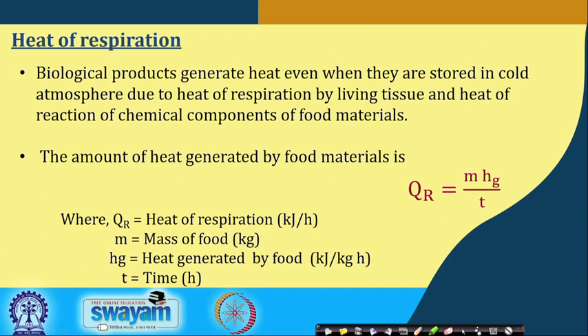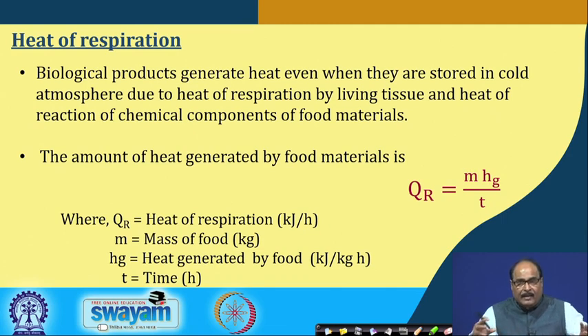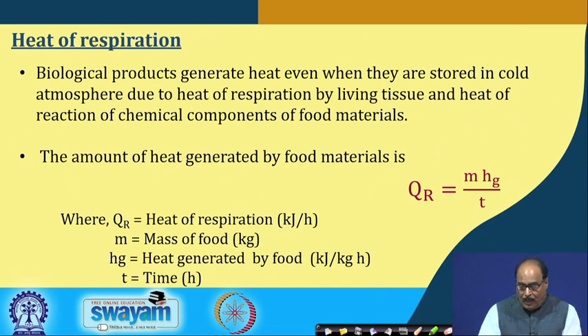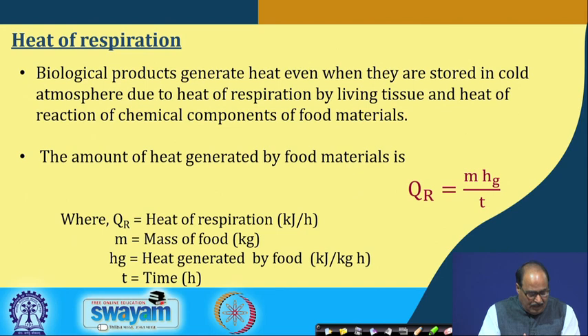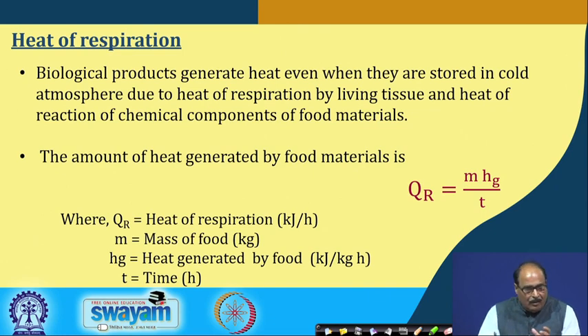The heat of respiration: all biological materials, when put in the storage facility even in cold atmosphere, generate heat due to respiration. There are also certain chemical reactions which undergo inside the material which also produce heat. The amount of heat generated by the food material QR may be equal to M·Hg / t, where M is the mass of the food, t is the time, and Hg is the heat generated by the food in kilojoules per kg per hour. From this one can find out the heat of respiration or total heat of chemical reactions.